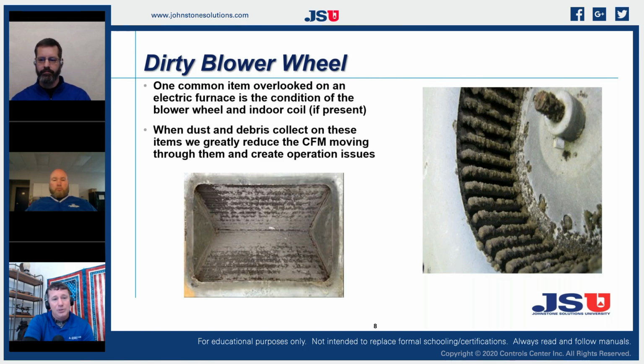If I were to use that previous calculation for my temperature rise, and say I've got an ECM blower motor that should keep a constant airflow, right? And I set my dip switches to run 1200 CFM. And I should be running about a 35-degree temperature rise, but I put my temperature probes on my return and my supply, and I go, wow, I've got a 45-degree temperature rise on the system. For some reason, I am not moving the 1200 CFM that this blower is supposed to be moving.